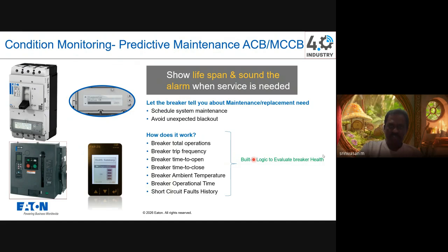Also, we have another interesting feature, condition monitoring in the ACB and the MCCB. Normally, assume you have an ACB that is 10 years old. It's working perfectly. Generally, most manufacturers and the FM team know very well that the ACB gives a lifetime of 10 years, 20 years also. But the point to be noted is, after 5 years or 10 years, we don't know whether the breaker is still okay or not. Can we continue with the breaker for a longer time or not? We are not aware. The FM team will not be knowing actually.